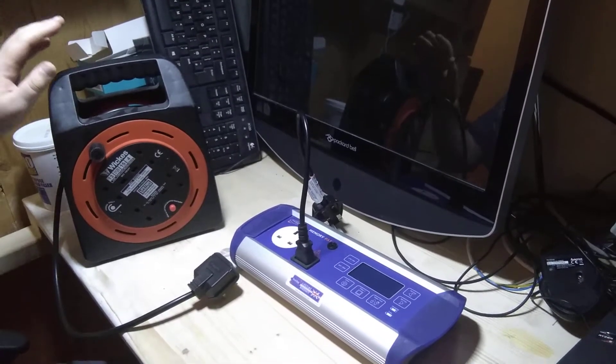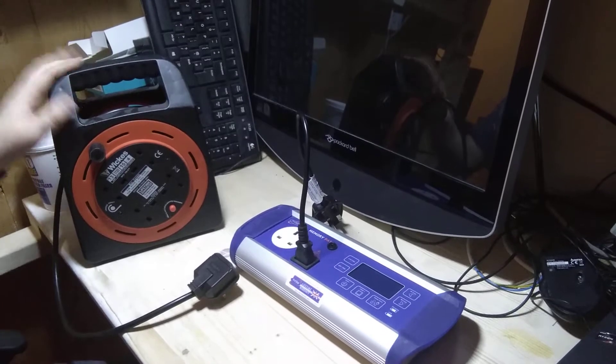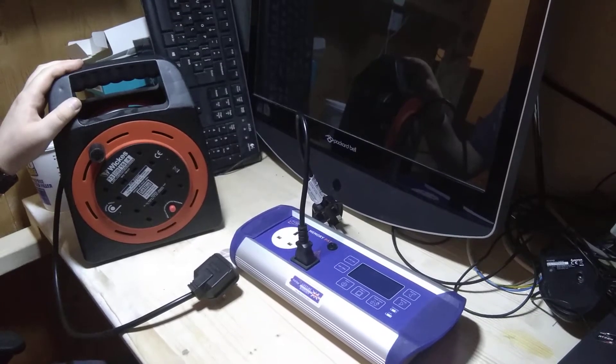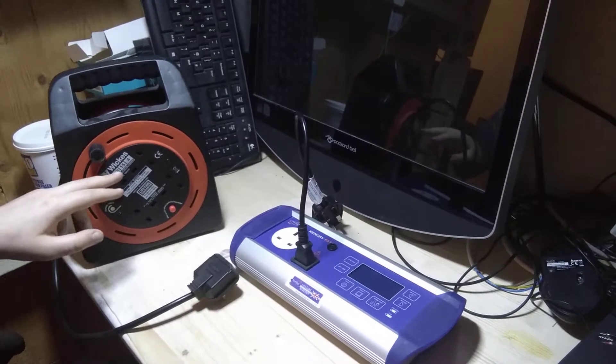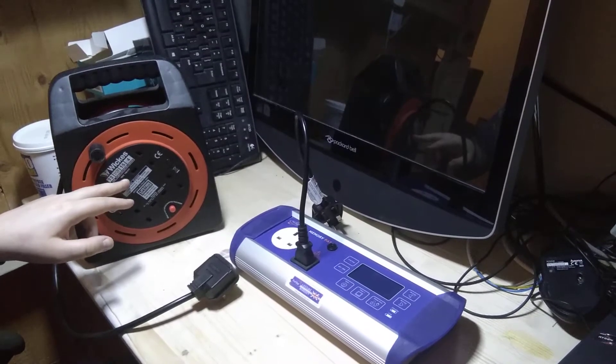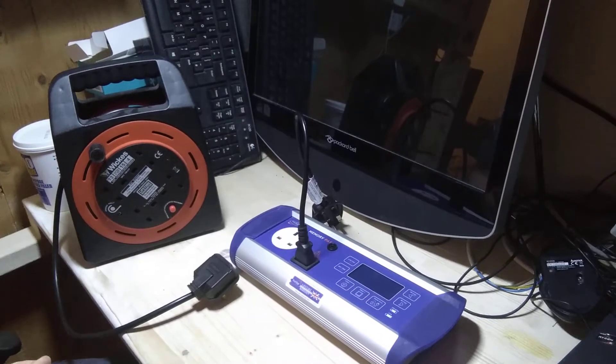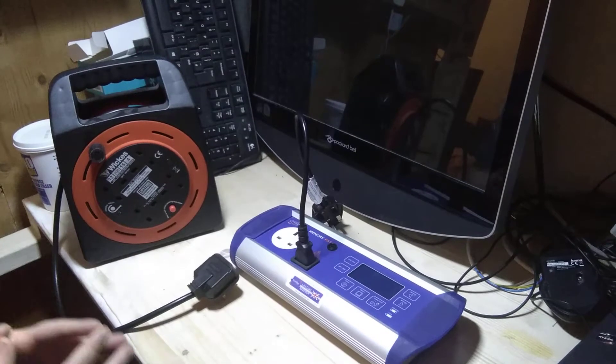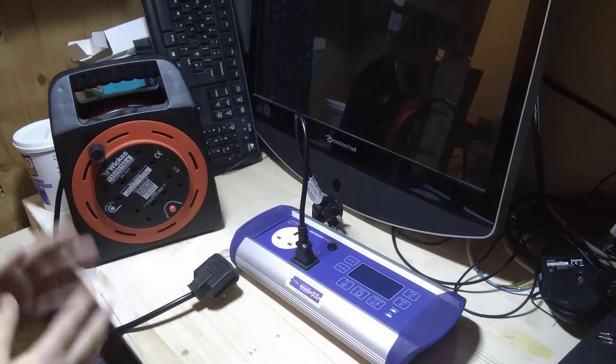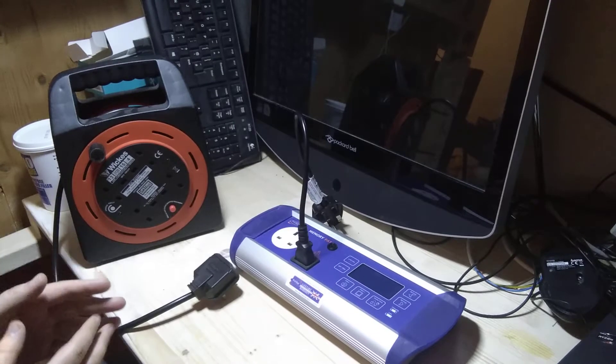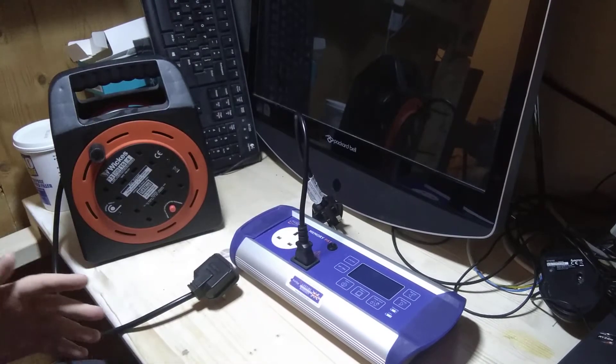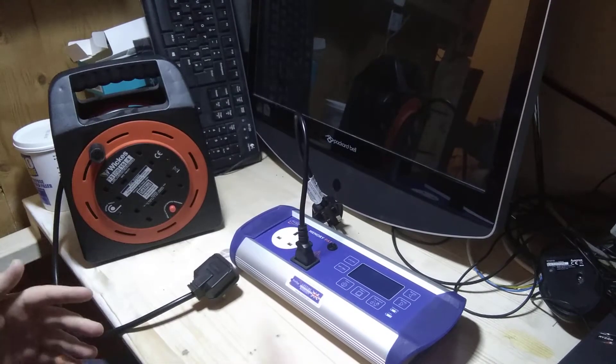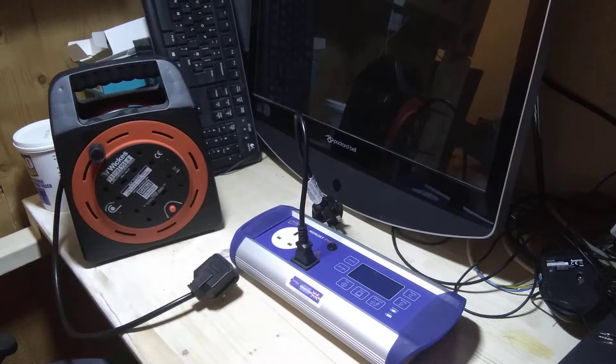It does require a bit of skill when you're testing long mains extension leads. This one is a 15 meter. A lot of PAT testers don't have the capability of testing long mains extension leads over 10 meters. If you're PAT testing over 10 meters, you need a machine that's capable of doing so.